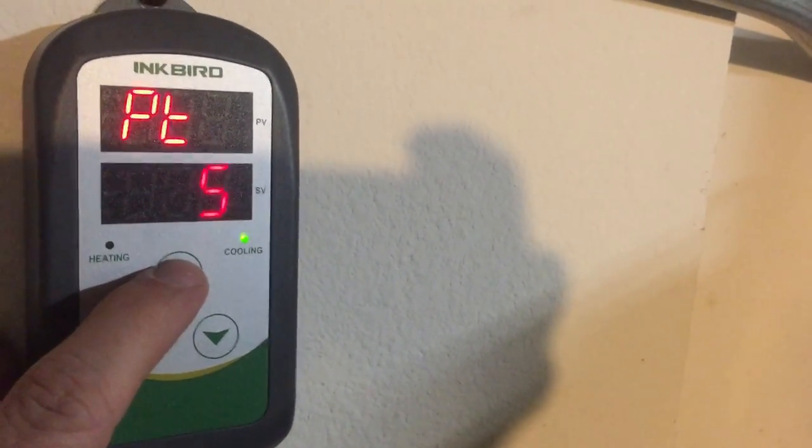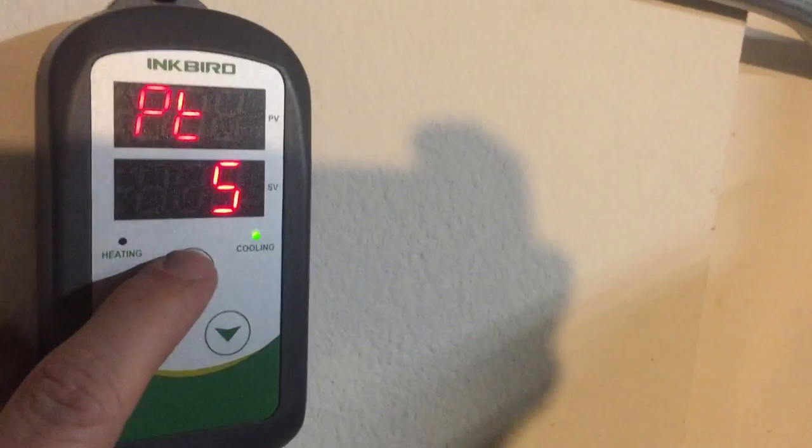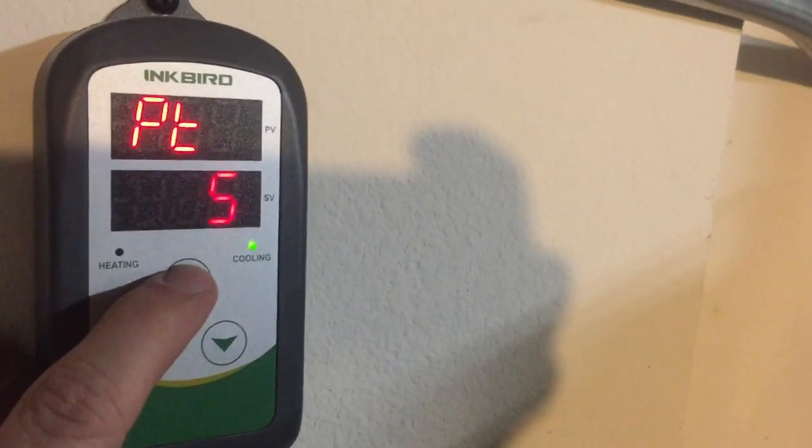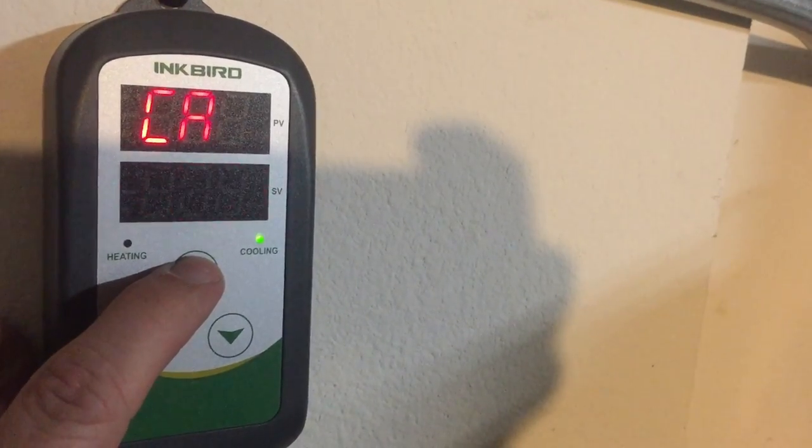The PT, that is the compressor pause, and that is at 5 minutes. The CA, that's your calibration. That's when you go to calibrate your thermometer. Mine just happened to be at negative 0.9.